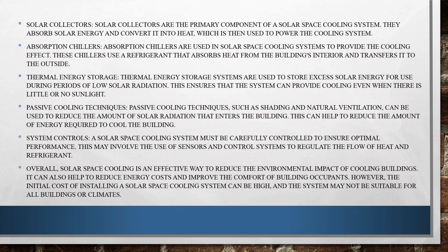Firstly, solar collectors. Solar collectors are primary components of space cooling systems. They absorb solar energy and convert it into heat, which is then used to power the cooling system. Absorption chillers are used in solar space cooling systems to provide the cooling effect. These chillers use a refrigerant that absorbs heat from the building's interior and transfers it to the outside. Thermal energy storage. This system is used to store excess solar energy for use during periods of low solar radiation, which ensures that the system can provide cooling even when there is little or no sunlight.